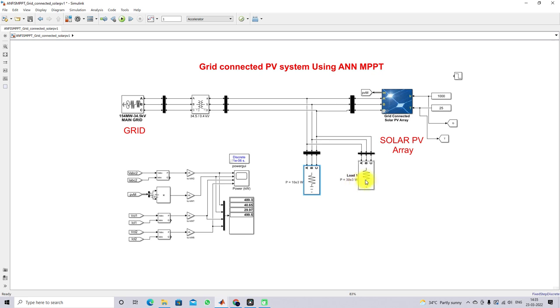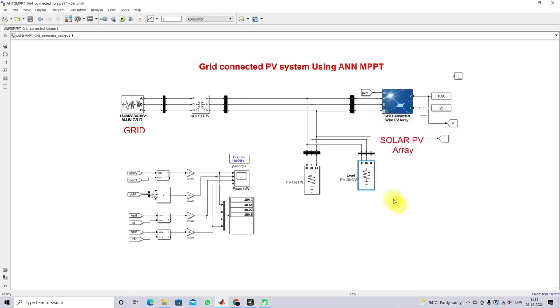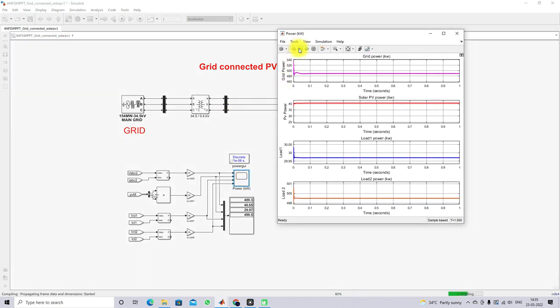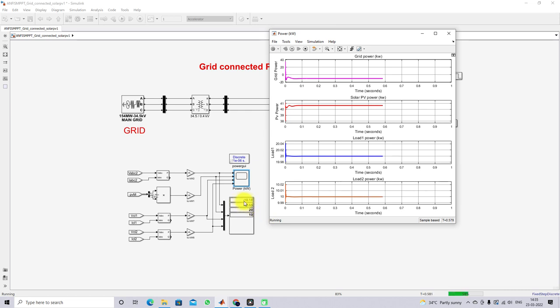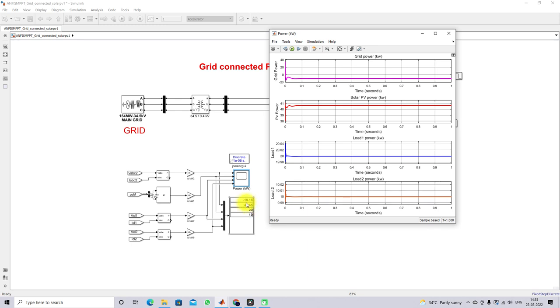Now I'm going to change the load condition. Load one is set to 10 kilowatts and load two to 20 kilowatts, so totally 30 kilowatts. The solar PV can supply a maximum of around 40 kilowatts, so the remaining 10 kilowatts should be sent to the grid. As we can see, the grid is receiving 10 kilowatts: PV generates 40 kilowatts, supplies 30 kilowatts to the AC loads, and the remaining 10 kilowatts is sent to the grid.